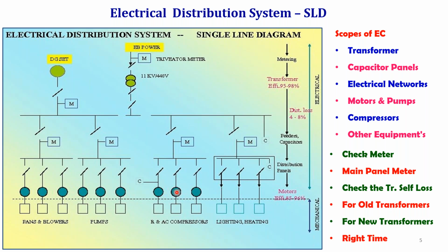But it is the right time to check each and every point, which may sometimes be important, sometimes critical also. Now you can see there is a C. C is a capacitor. Capacitor is connected in the main MV panel. Capacitor is connected on the individual motor side and individual load side. Capacitor is also connected at the sub-distribution panel also. So it is the right time to justify where we have to fix the capacitors.